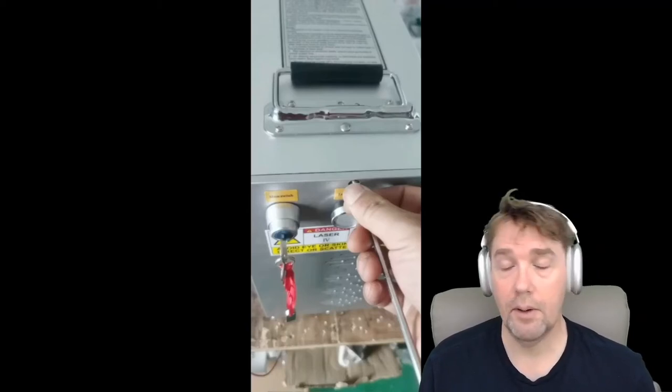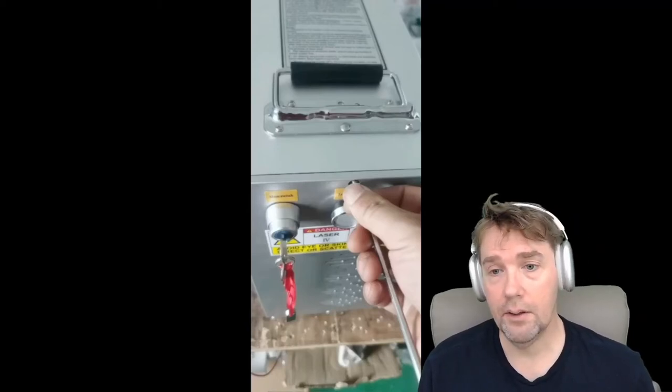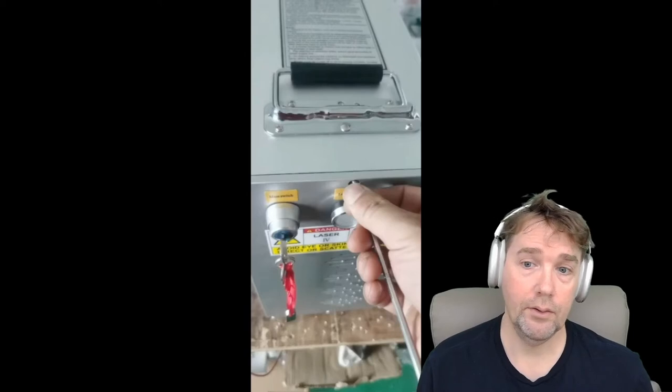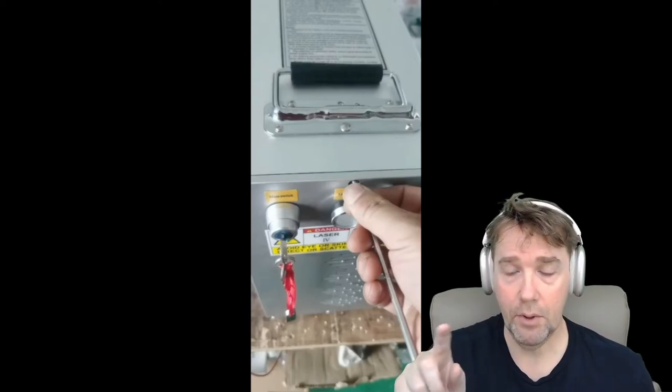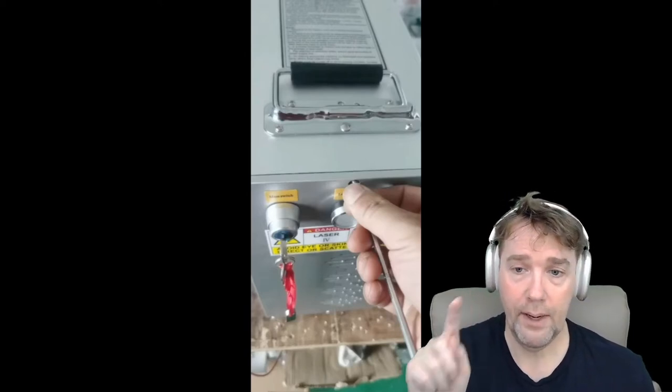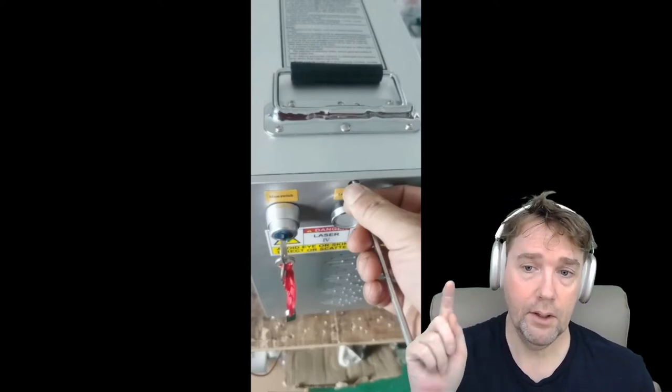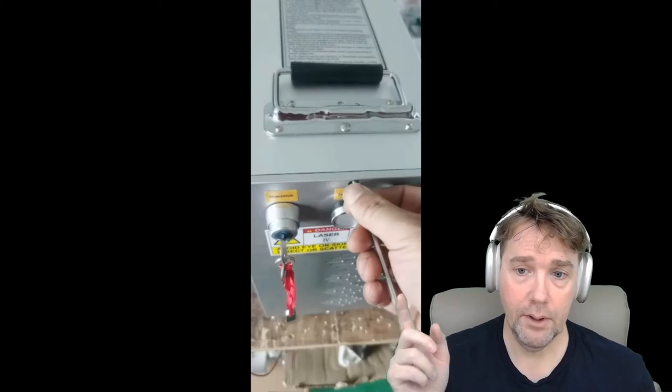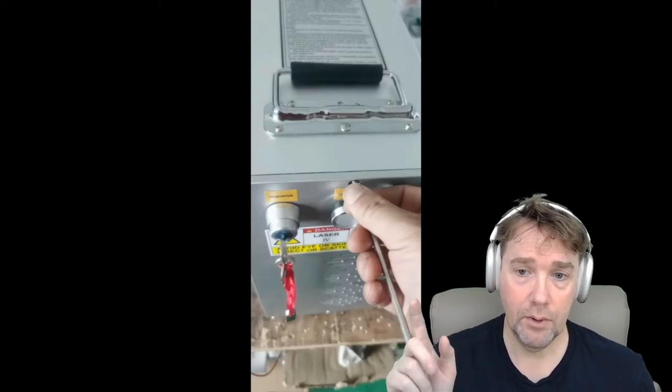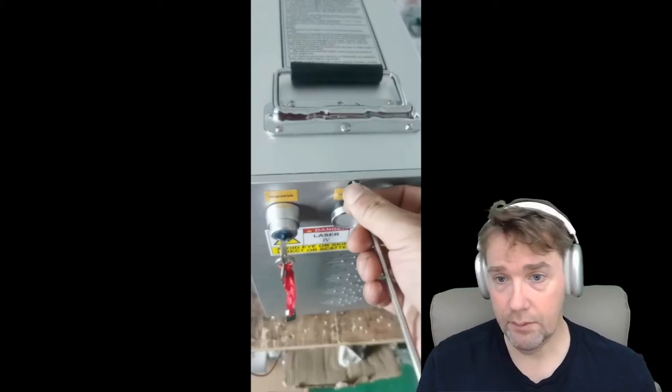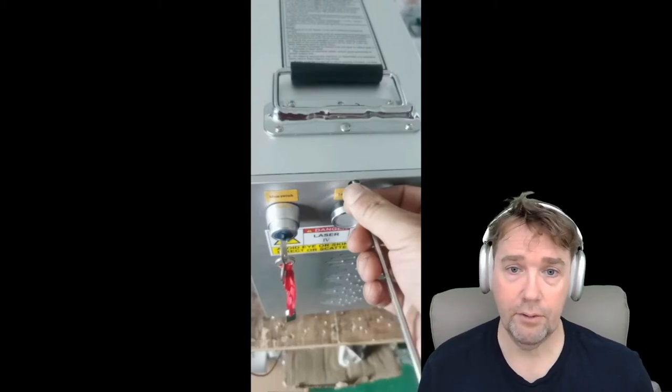Hi, the galvanometer on my fiber laser died and this is how to debug if you have a problem with the power supply or the galvanometer itself. This is how you check if there's a power supply fault.